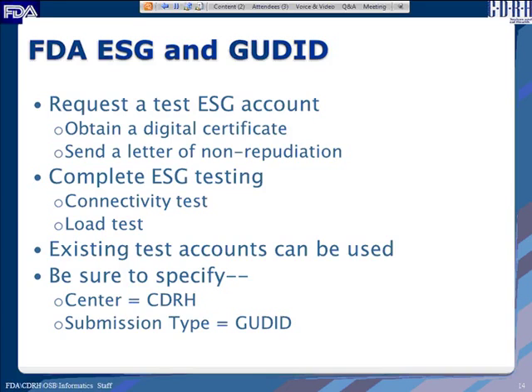Once ESG testing is complete, you can begin testing for GUDID. Be sure to specify the center as CDRH and the submission type as GUDID so that the gateway routes it to the correct center and CDRH can route it to the appropriate parser.